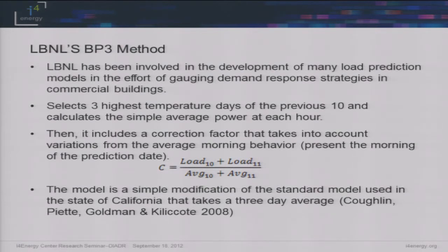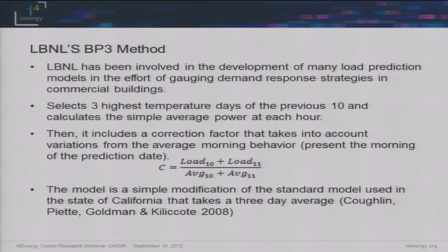LBNL's Marianne Piette and Sila have worked on a lot of different model development. They have a paper with nine or ten models that have been developed, and they go through calculating the error, bias, and similar metrics. So I felt like keeping with that strategy for assessing our model made sense. The BP3 method selects the three highest temperature days of the previous ten and calculates a simple average of power for each hour. Then they have a morning correction factor which uses the demand at 10 a.m. and 11 a.m. of that morning, adds those together, and divides by the average of 10 and 11 for those three highest temperature days. It's a simple modification of the standard model, but the correction factor makes it better.